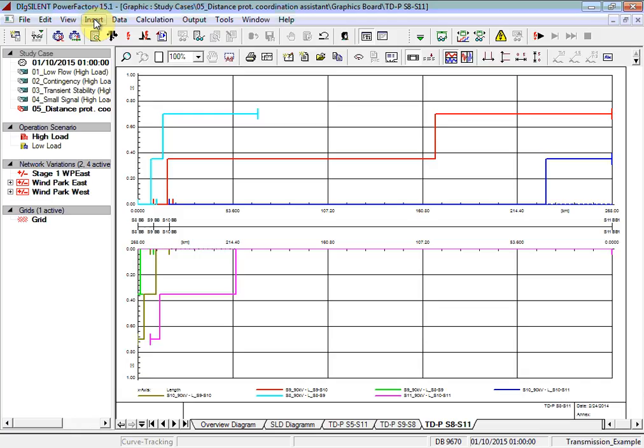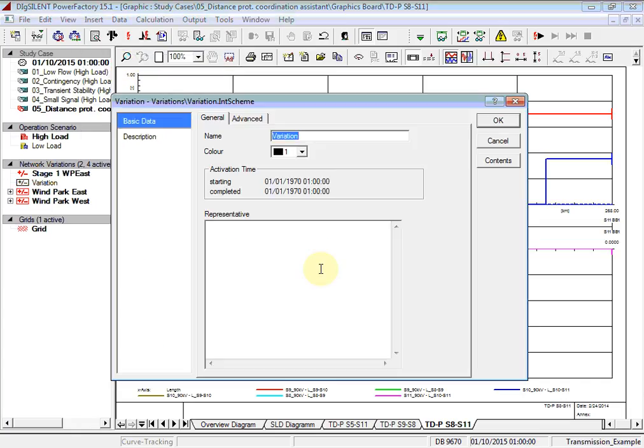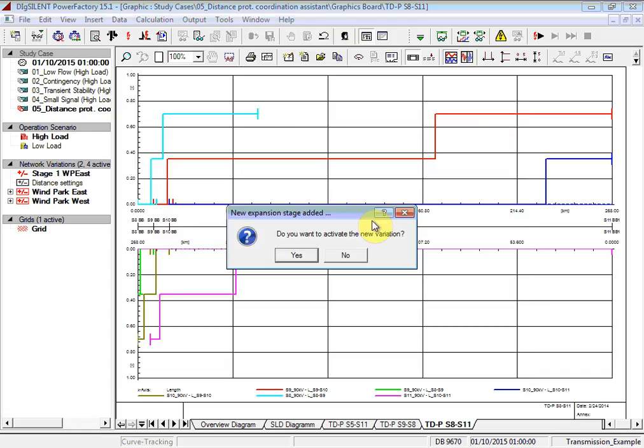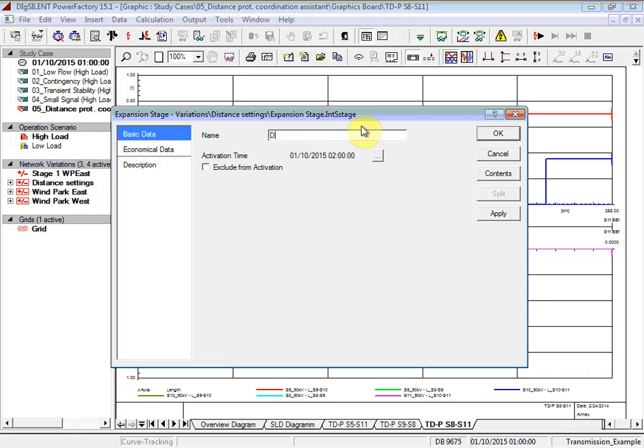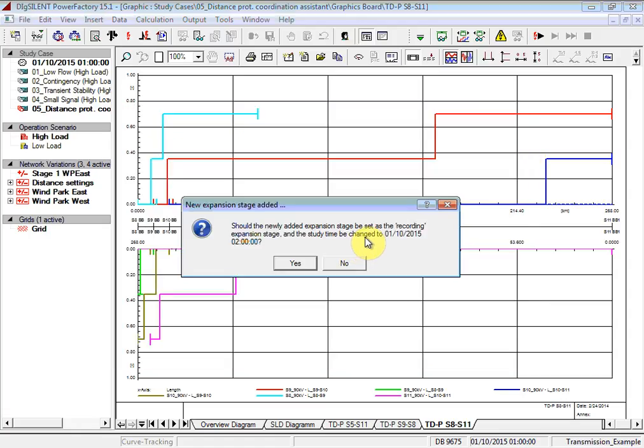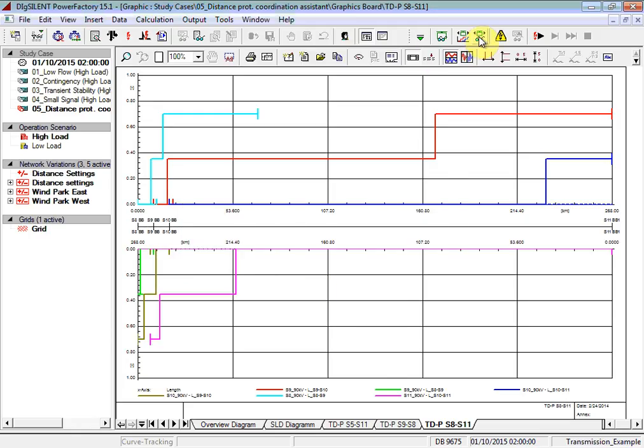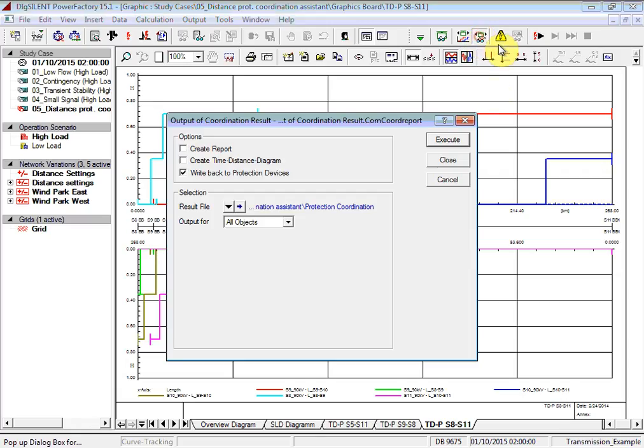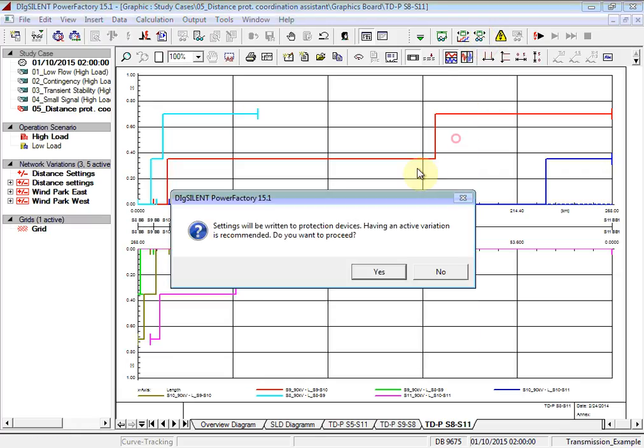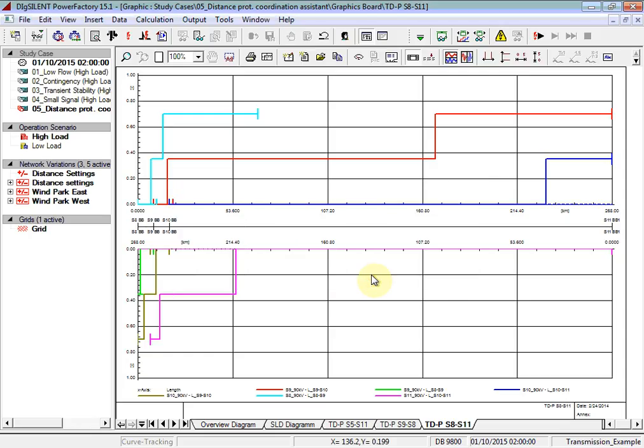Choose No and select the option Insert Variation. Name the variation Distance Settings or similar and select OK. Choose to activate the new variation and name the expansion stage as well. Choose to set the new expansion stage as the recording expansion stage. Choose the option again, Output of Coordination Results, and select Execute. This time select Yes. The settings have now been written back to the protection devices installed in the network.